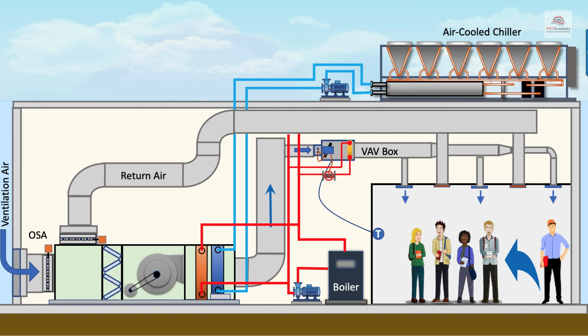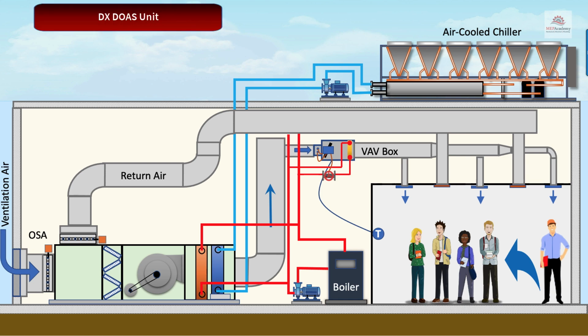We can decouple the latent load from the sensible load by adding a DX DOAS unit. Then the air handler's chilled water coil can be downsized, including the chiller, pump, and piping. This savings is offset by the addition of another piece of equipment, the dedicated outside air system, which is dedicated to treating the ventilation air in an indirect or direct configuration, which we'll discuss shortly.